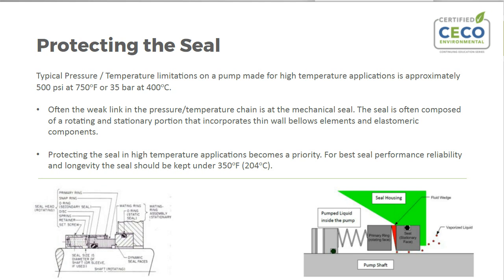The typical pressure and temperature limitations on a pump made for high temperature applications are approximately 500 psi at 750 degrees F, maybe that's about 35 bar at 400 degrees C. This limitation is made to maintain proper operation. The actual structure of the pump components can withstand much higher conditions. Safety factors for the pump pressure vessels generally run anywhere from 1.5 to 3 times the design conditions.